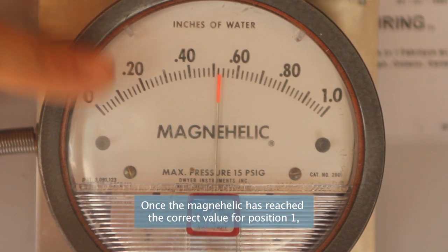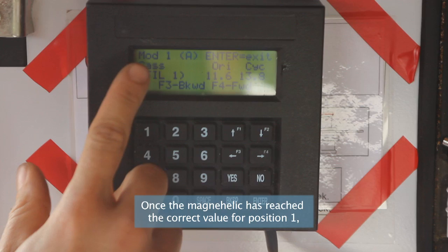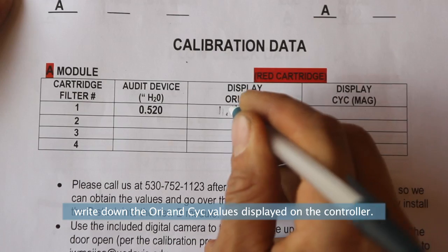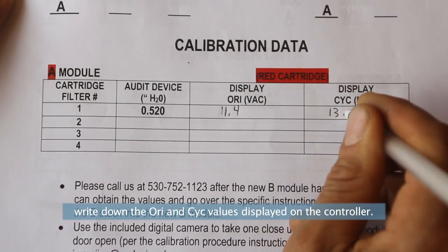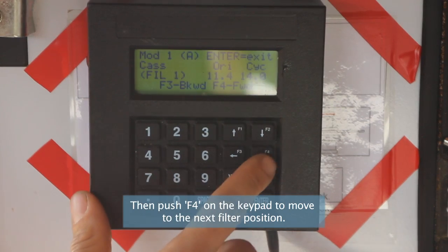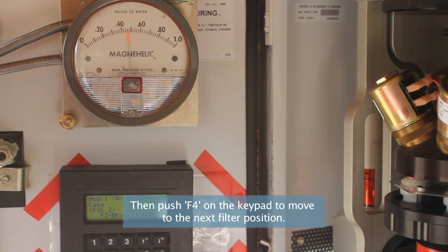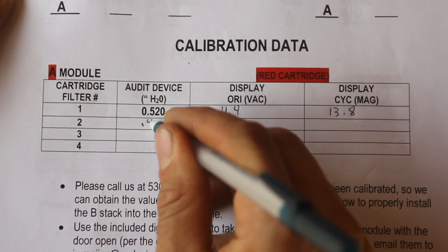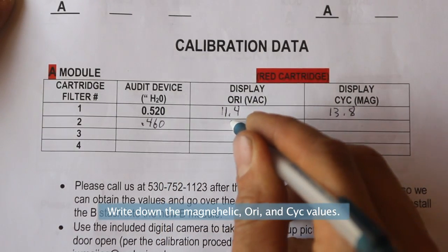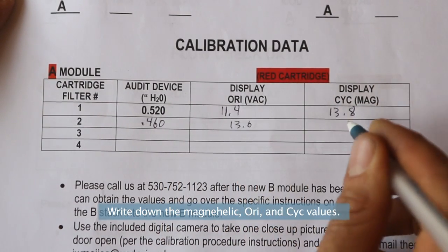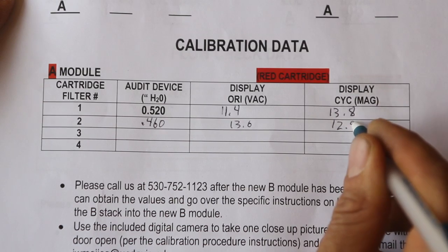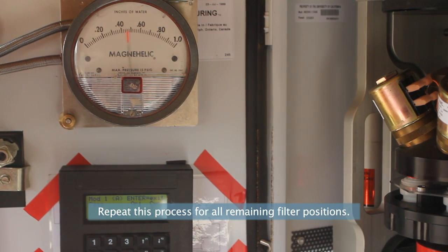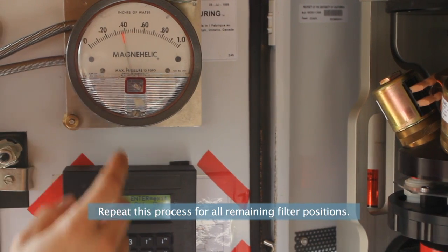Once the magnehelic has reached the correct value for position 1, write down the ORI and CYC values displayed on the controller. Then push F4 on the keypad to move to the next filter position. Write down the magnehelic, ORI, and CYC values. Repeat this process for all remaining filter positions.